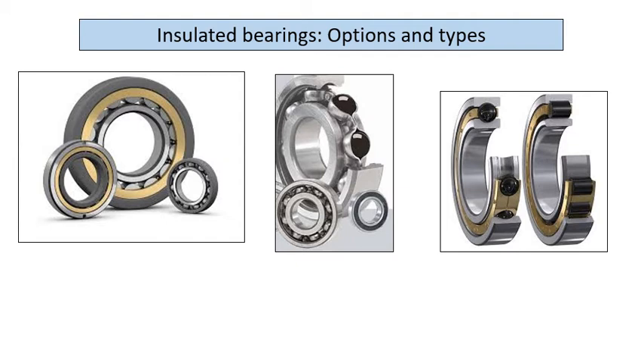Okay, the insulated bearing types: those are the ceramic coating, and the next one is ceramic rolling elements. They're made of silicon nitride. I've heard the good thing about them is that they don't need lubrication because the friction is so low on these rolling elements that SKF say they don't need lubrication, so they run indefinitely. But I came across an end user in the Netherlands that is right on the cutting edge of bearing speeds with their application. The application is rotary UPSs, and they used some of these bearings, and they found that the uniformity of the rolling element geometry is not fully up to scratch. So ironically they had problems with that. And of course, it's fully insulated because your inner ring is completely insulated from your outer ring, but you need to make sure that you have a non-conducting cage.